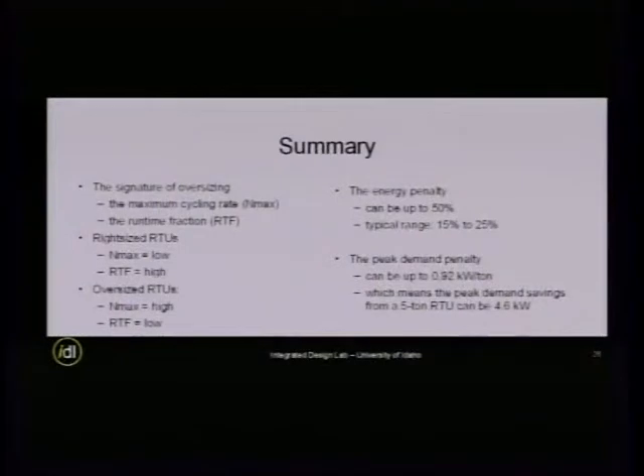Now, the energy penalty can be up to 50% based on our data. The variation of data is not that great, but we can say that it can be up to 50%. The typical range is between 15 to 25%, which confirms the old data from the literature. And the peak demand penalty, this is one of the important results, is 0.9 on average, 0.9 kilowatt per ton.